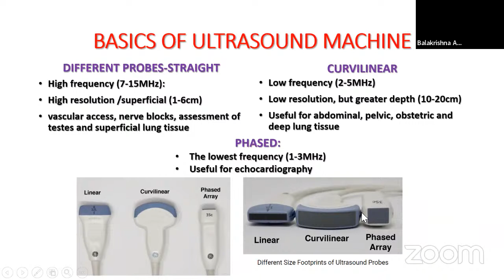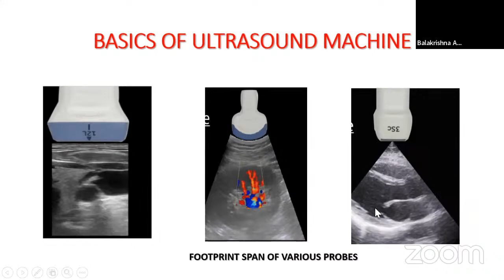So this slide shows how an image is generated when the ultrasound beam passes through the tissue. The tissues reflect back the image and what we get on the screen. So this is the image that is seen when we use the straight probe. This is the image that we get to see when we use a curvilinear probe, and this is the phased array probe, usually used to visualize the cardiac. And what we see is called the footprint span. This is the footprint span of a linear probe. This is the footprint span of a curvilinear probe, and this is the footprint span of a phased array probe.